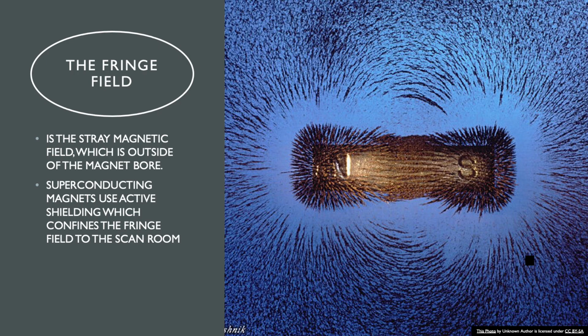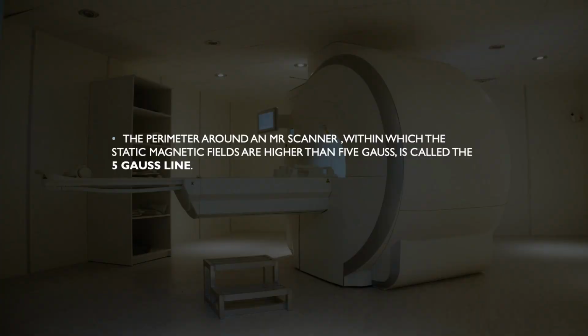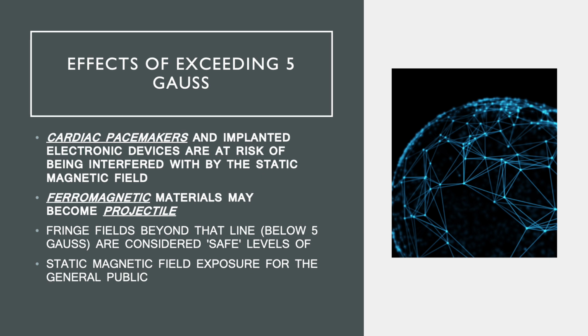The stray magnetic field, which is outside the magnet bore, is known as the fringe field. Superconducting magnets use active shielding, which confines the fringe field to the scan room. The perimeter around an MRI scanner within which the static magnetic fields are higher than 5 gauss is called the 5 gauss line. This is about 10 times higher than the average Earth magnetic field. A few changes are expected upon crossing the 5 gauss line. At 5 gauss line and above, cardiac pacemakers and implanted electronic devices are at a risk of being interfered with by the static magnetic field.